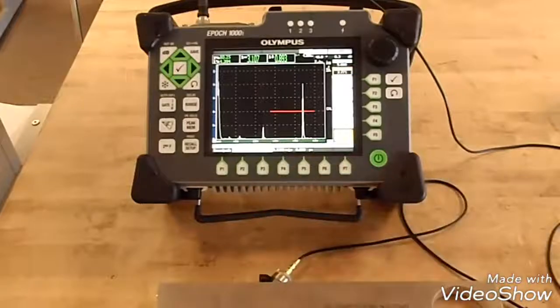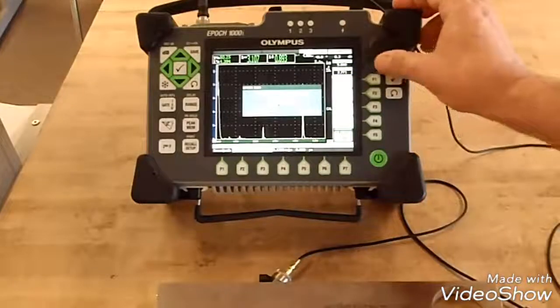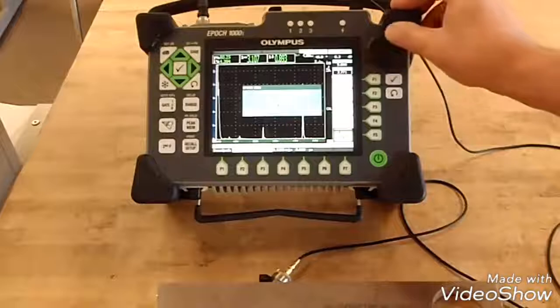Cal your velocity, telling the system that that's a four inch sound path.